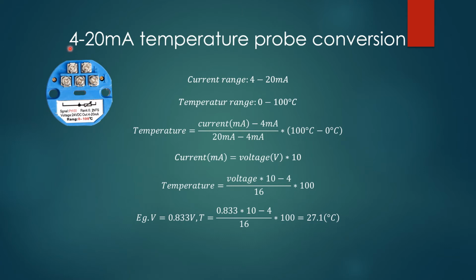In this video, I will explain how to read a temperature probe from a 4 to 20 milliamp temperature loop. In order to do this, first you need a temperature probe, second you need this transducer, and then you'll also need an SDI12 USB adapter with a 4 to 20 milliamp current loop sensor extension board. So let's take a look at this transducer.